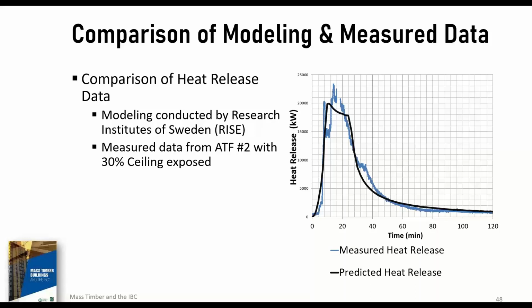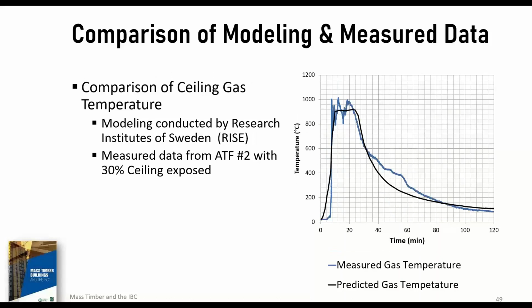So some modeling research that was conducted by the Research Institute of Sweden, or RISE, estimated with their modeling that the heat release rate data should be approximately 20 megawatts. It ended up being a little bit more robust than that, but you can see with the black line the projection matched really pretty closely with the data that was recorded at the ATF. Correspondingly, if we look at the ceiling gas temperature, again, with some spikes and ups and downs, and a little bit more than they anticipated, which is good for making sure your testing is robust, but a fairly steep rise, a plateau, and then a decline. So there's a little bump there in the actual data, but it's just a downward trend is what we're looking for. And of course, no post-secondary flashover.